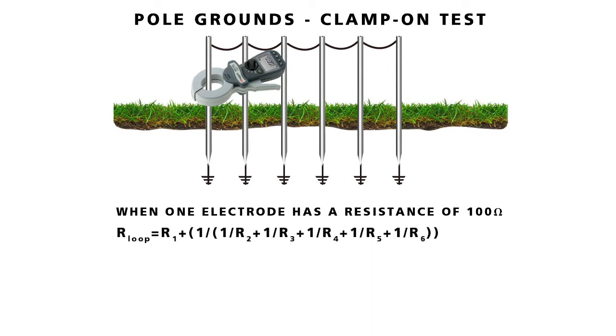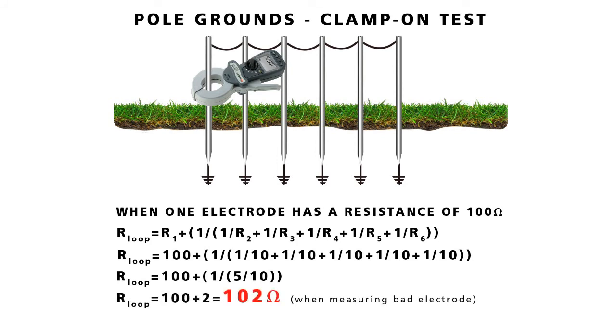How can the clamp-on identify a bad ground in an otherwise good string? Calculation shows that a 100 ohm ground in parallel series with 5 10 ohm grounds would read 102 ohms, readily identifying the problem.